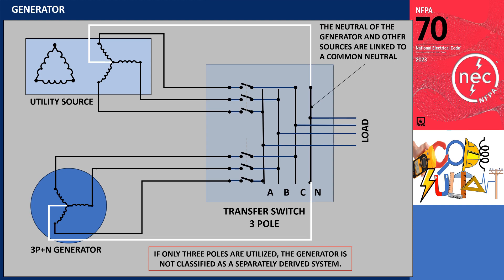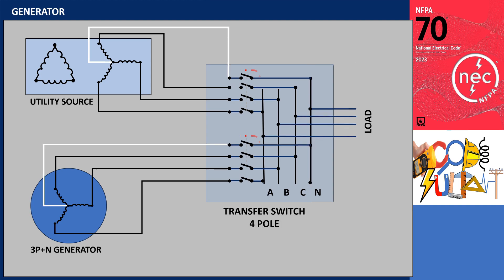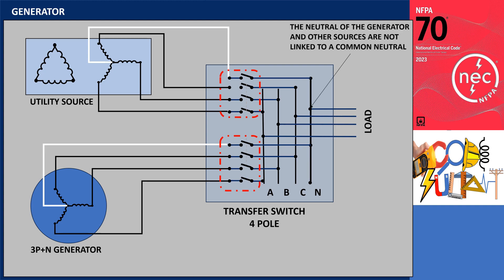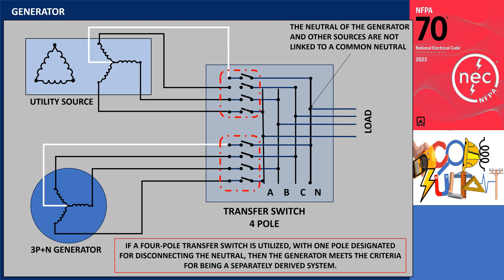If only three poles are utilized, the generator is not classified as a separately derived system. However, if a four-pole transfer switch is utilized — with one pole designated for disconnecting the neutral — then the generator meets the criteria for being a separately derived system.